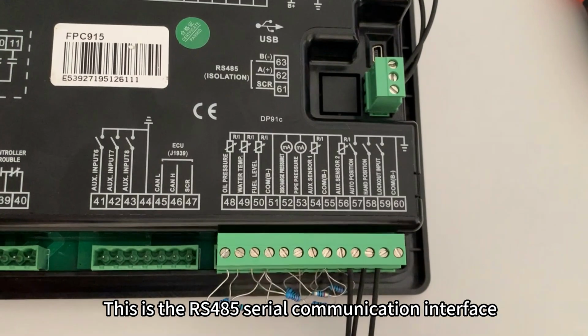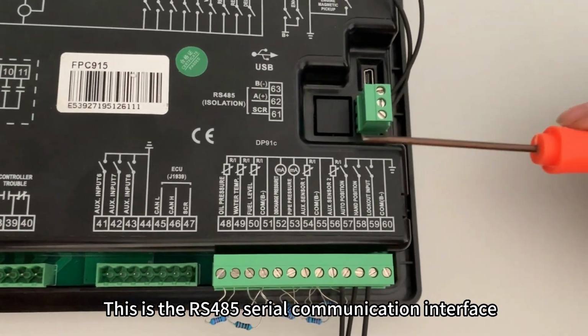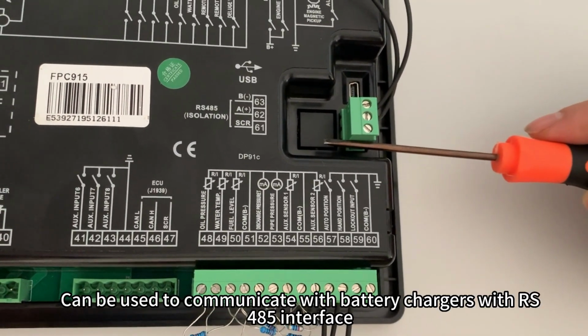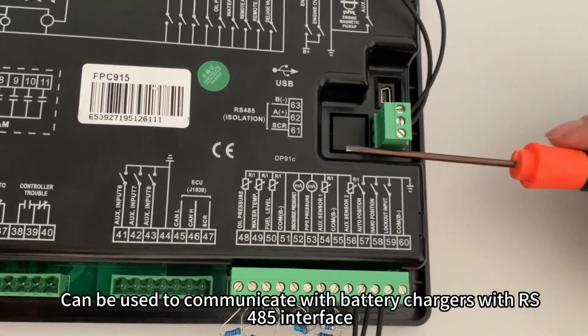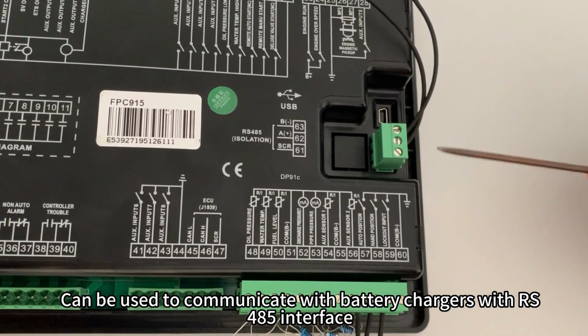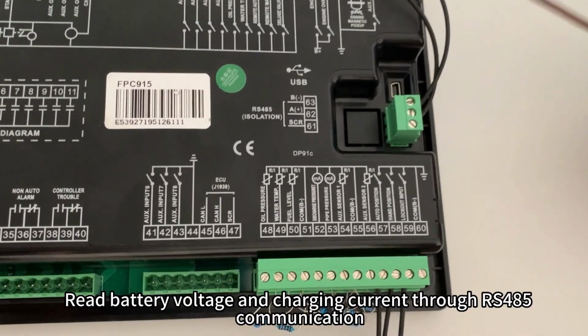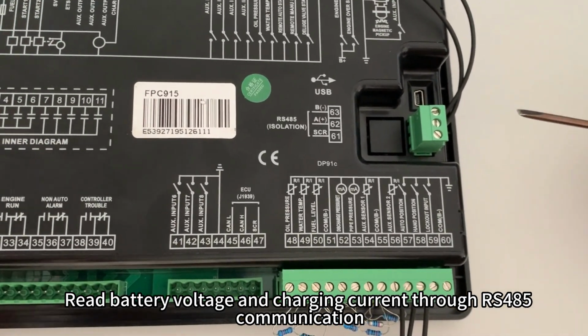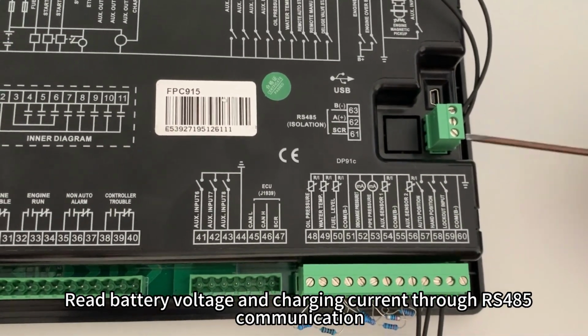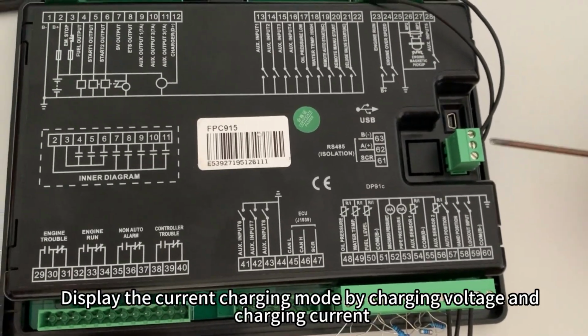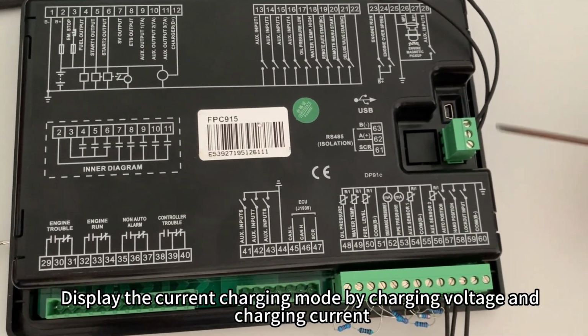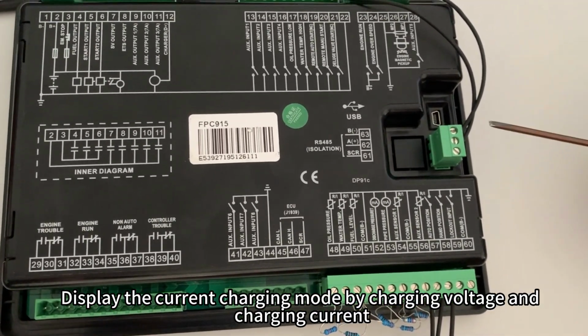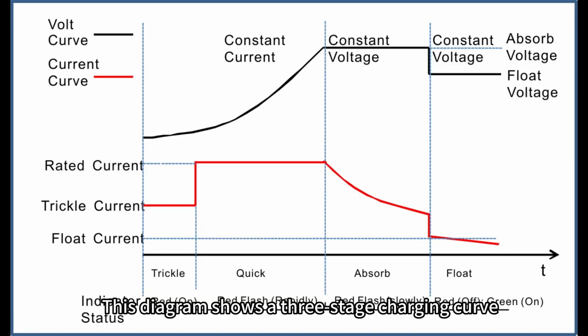This is the RS485 serial communication interface. It can be used to communicate with battery chargers with an RS485 interface. Read battery voltage and charging current through RS485 communication. Display the current charging mode by charging voltage and charging current. This diagram shows a 3-stage charging curve.